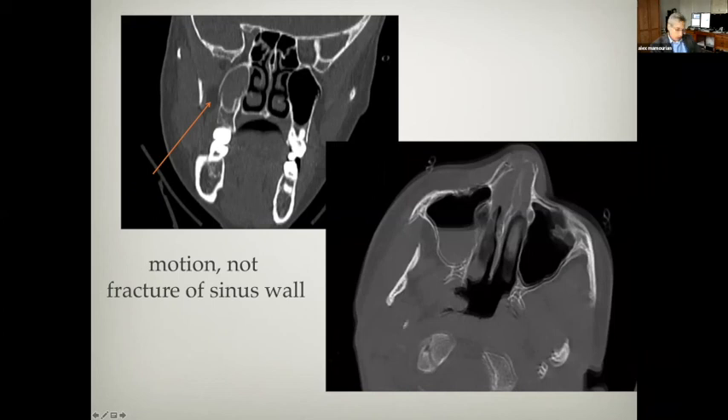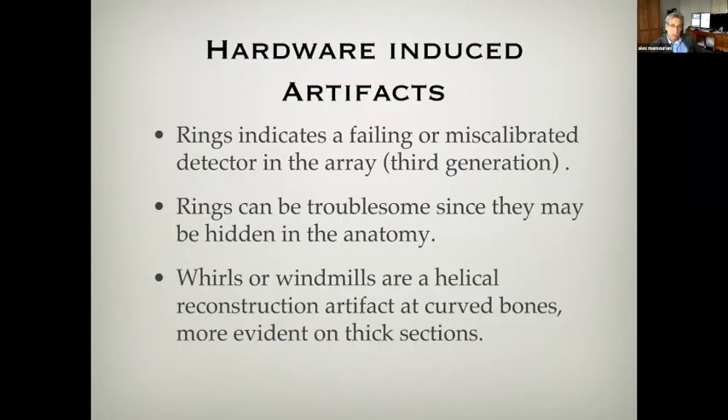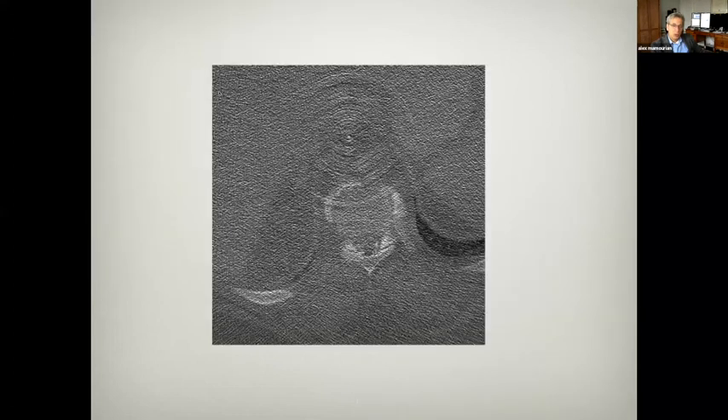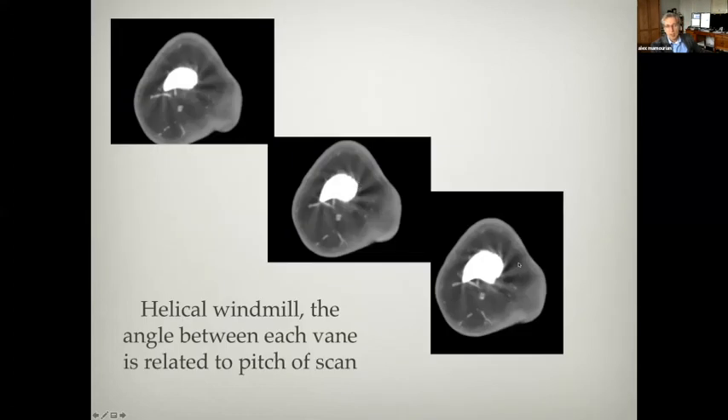Some artifacts are induced by the hardware. I'll show you examples of rings and whirls, which have to do with how the scanner is calibrated. This ring lesion is an artifact caused by failure of calibration of one of the detectors; here are multiple rings near the center of the image — a calibration error. These whirls are a feature of helical imaging, particularly with relatively thick slices, and the angle between the vanes is related to the pitch of the acquisition — artifacts caused by the hardware and the reconstruction.